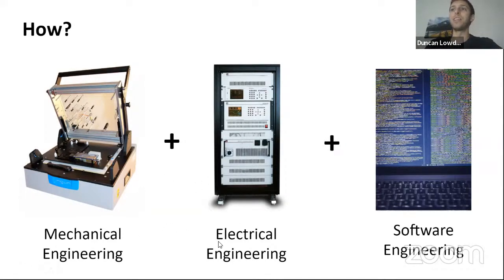And then the last component is the software engineering, because you need to develop an automated test plan or test software that will run through all the tests so that an operator doesn't have to sit there on the factory floor manually checking voltages or looking at readings.